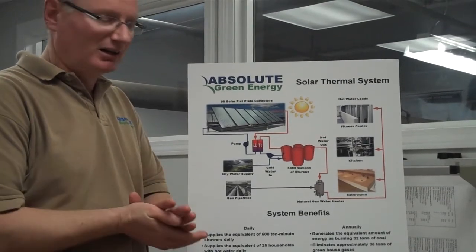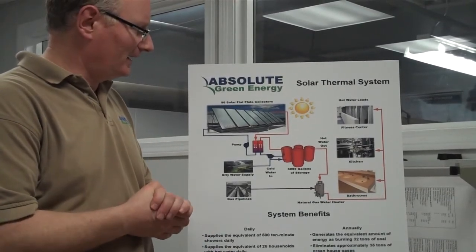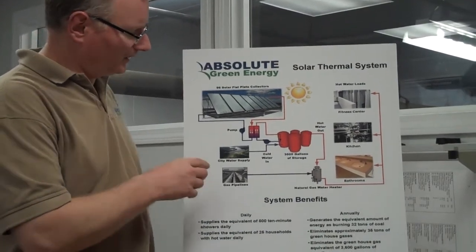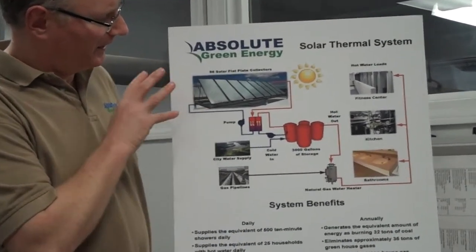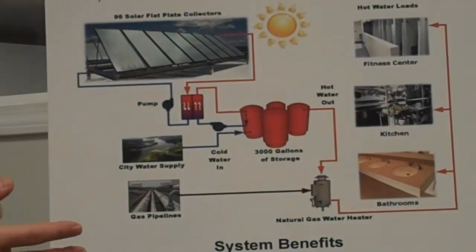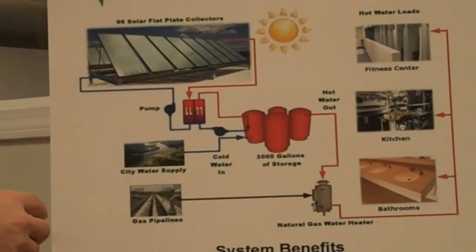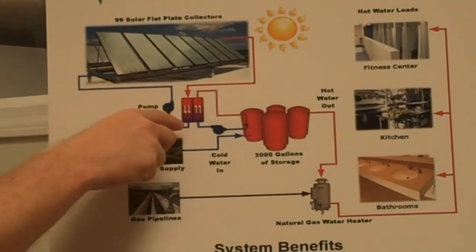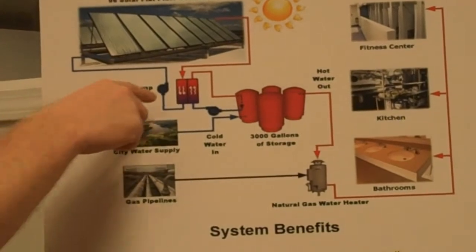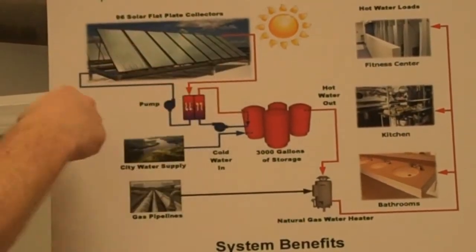It consisted of 96 collectors. The way these systems work: you basically have a set of collectors on the roof of a building, or it could be a ground-mounted application. There's a heat transfer fluid, which is typically water or a mixture of water and propylene glycol, that circulates through these collectors.